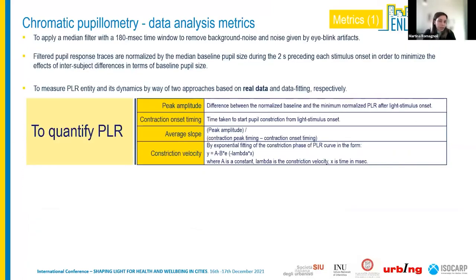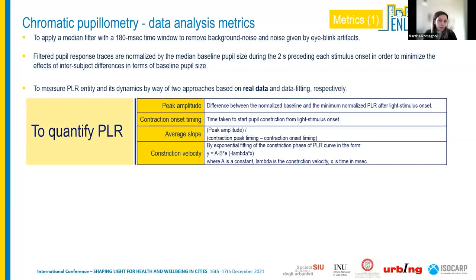Our data approach applies a median filter to remove background noise and blink artifacts. The filtered pupil response traces are normalized by the median baseline pupil size to minimize effects of biological inter-subject differences. We can then measure PLR magnitude and dynamics through two approaches: one based on real data — calculating parameters like peak amplitude, contraction onset timing, and average slope — and a second based on data fitting, estimating parameters like constriction velocity.